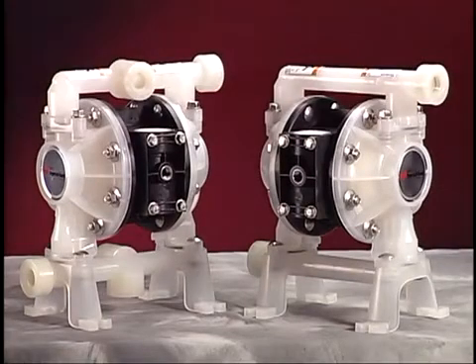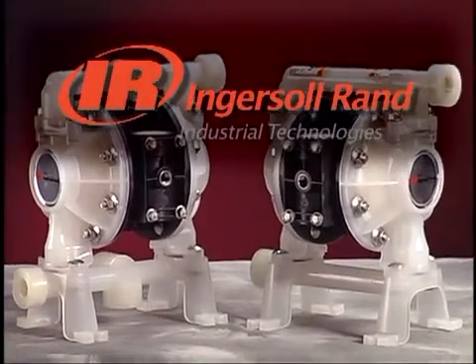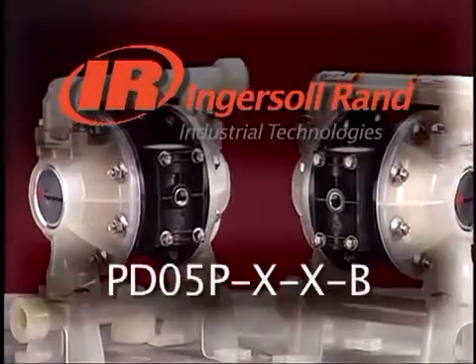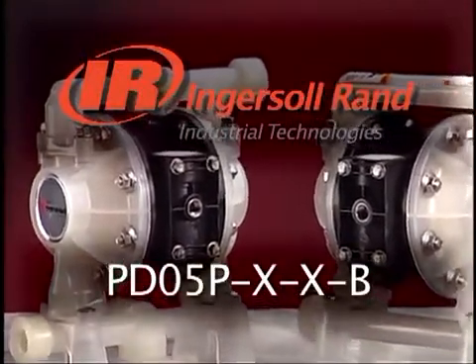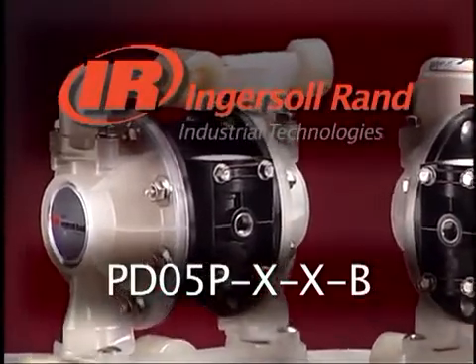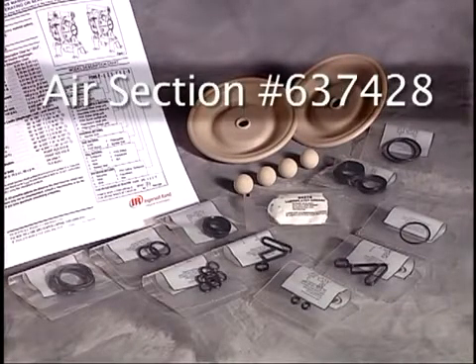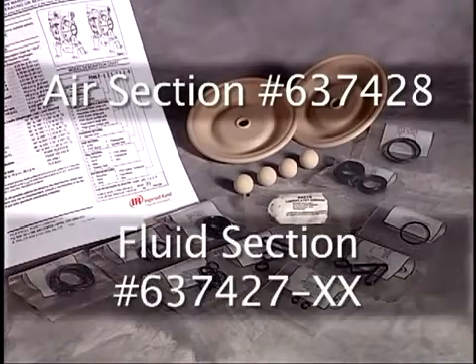This program outlines maintenance procedures for the Ingersoll Rand ARO 1/2 inch nonmetallic diaphragm pump model number PD05P-X-X-B. When repairing an ARO 1/2 inch diaphragm pump, always use genuine ARO service kits. To repair the air section of the pump use kit number 637-428. To repair the fluid section of the pump use kit number 637-427-XX.